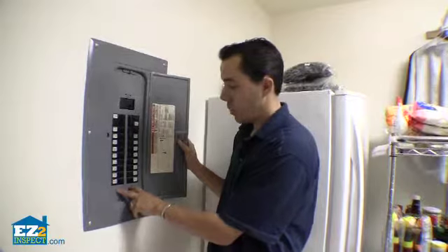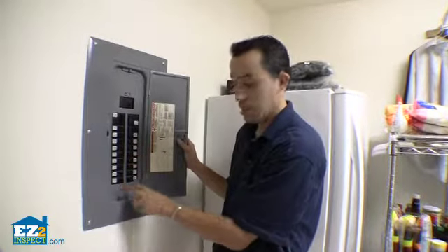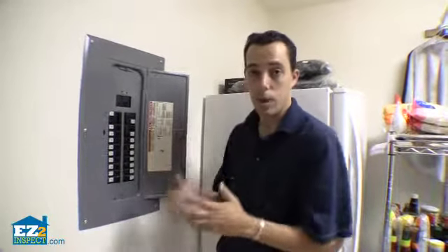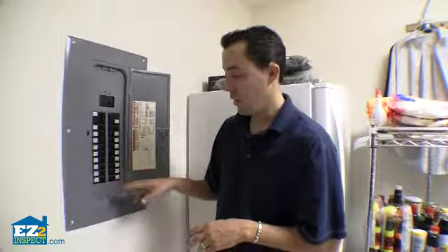Next, make sure there are no openings inside the electrical panel — meaning you can't stick your finger inside the electrical panel, a child can't, things of that nature. These are called twist outs right here, and those are the entry points for people putting things in.